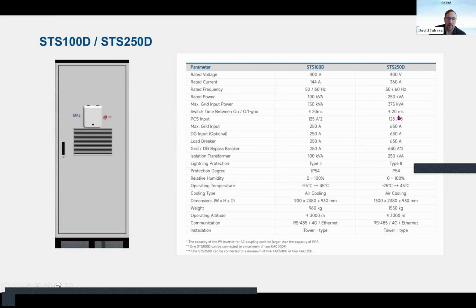is 5 pieces, and it has an isolation transformer inside to solve the protection of the off-grid system during the switchover, and it has a standard separate breaker for the grid, for the loads, for the diesel generator input, and also for the 2 hybrid inverters. Regarding the communication, it also has RS485, 4G and Ethernet, and the system is also for outdoor, so it's dust-proof and waterproof.